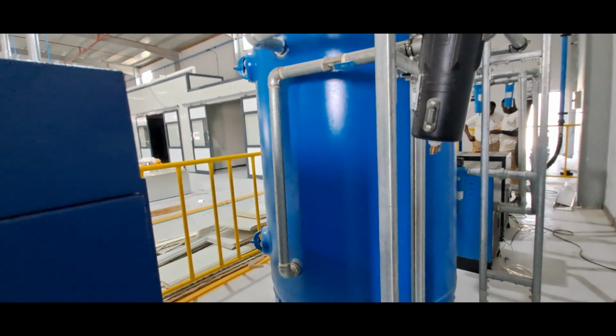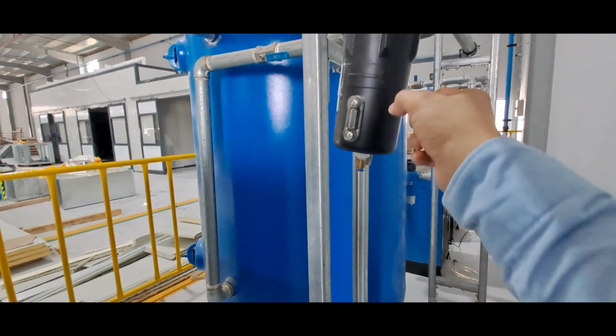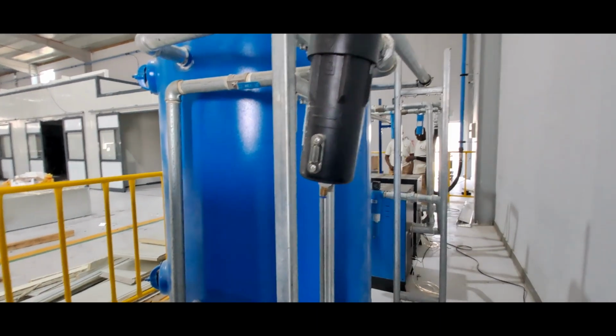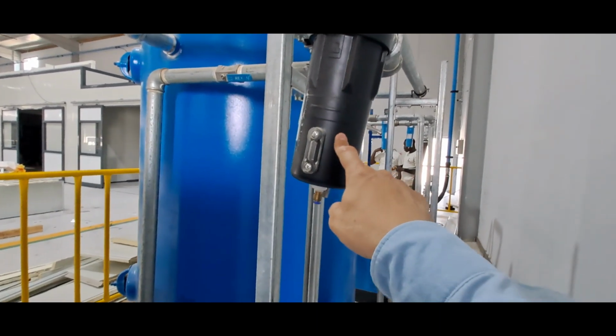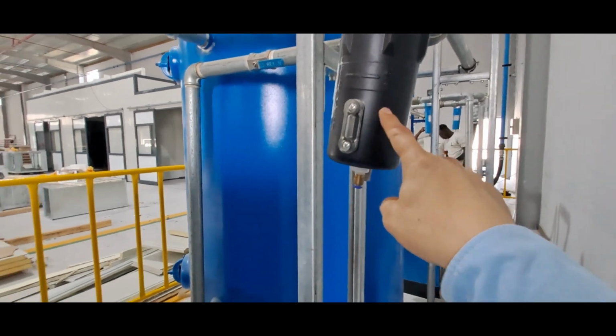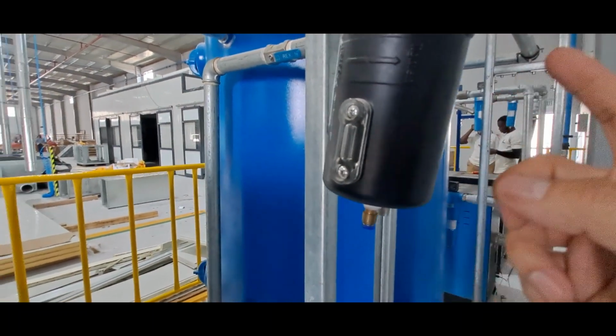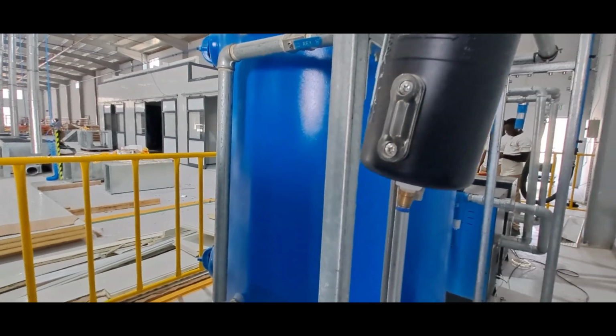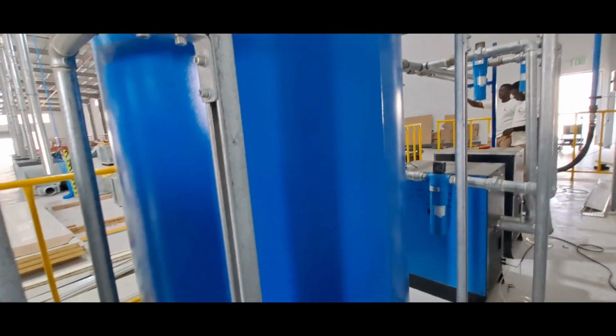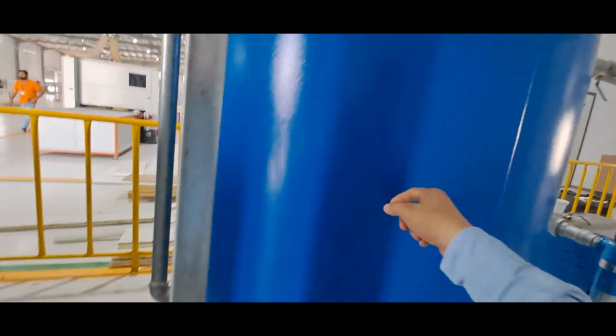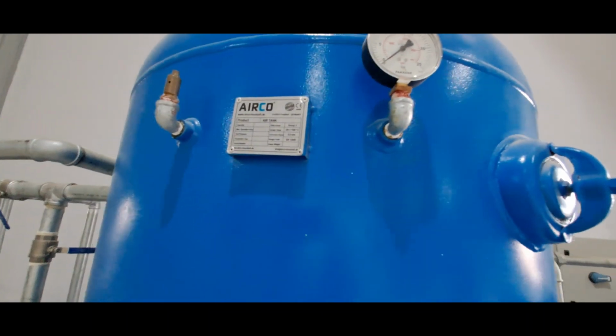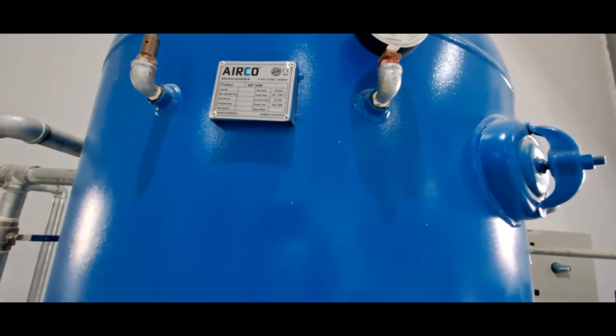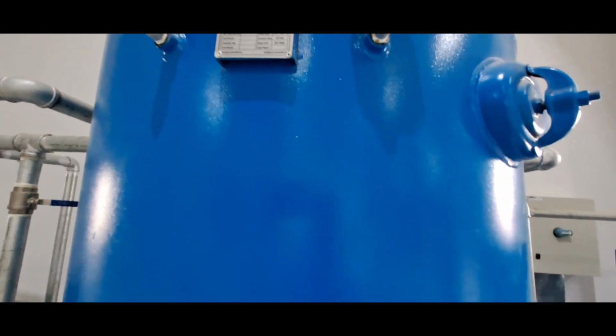Normally the setup from the air compressor goes to the header pipe, and then it goes to the air tank. Before getting inside the air tank, there is a filter here. This acts as a first stage filtration, so before any impurities, oil, or water goes to the tank, it is filtered through this filter. And then from the tank, you have the regulator, I mean the pressure gauge, and the pressure relief valve. In case of over pressure, this relief valve will discharge air pressure.